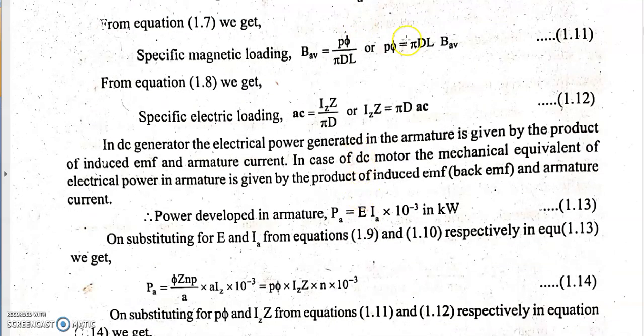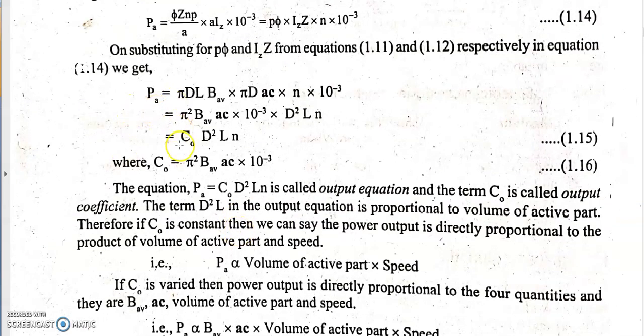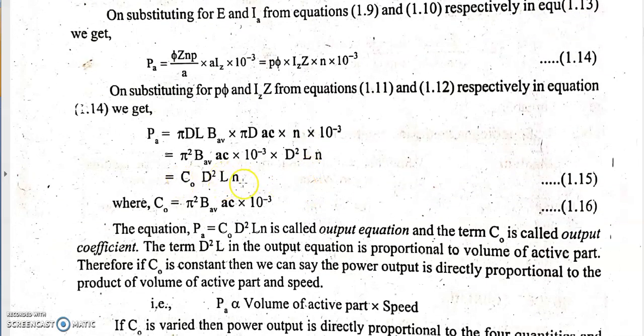Substituting for total magnetic loading and total electric loading using the specific loading equations — Pφ = πDL × B_average and Iz × Z = πD × AC — and separating terms, we obtain π² and D²L as one group, with B_average × AC as another. The term π² × B_average × AC × 10⁻³ is defined as C₀, the output coefficient of the machine. The output equation becomes: PA = C₀ × D²L × n.